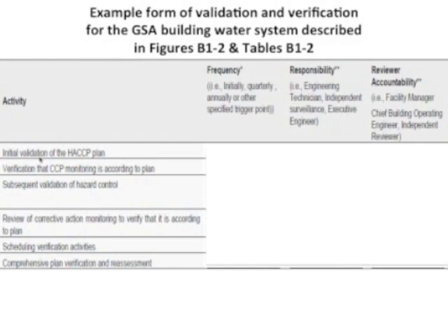But let me just say this. After many years of debate and consideration of all the issues regarding Legionella testing, here's what this committee has decided, and I believe quite rightly. Testing is very important. It can be very, very important. However, it must be acknowledged that, number one, testing for Legionella is not a means of control whatsoever. And even though that may sound silly to some of you and obvious, I can tell you from bitter experience that there are many folks selling Legionella testing who make the claim that it is a form of control, or it's so closely linked to a form of control that test results themselves can be relied upon for regulating control. This is not to be advised, nor recommended in any regard.